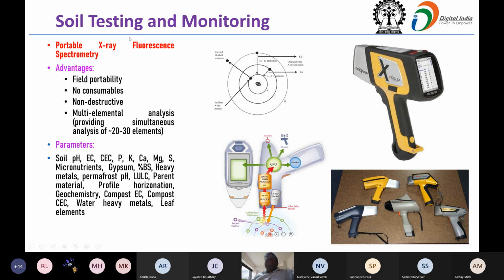Now let us start with the first one, that is called portable X-ray fluorescence spectrometry. It is a very small, handgun type of instrument, and you can see the size. You can carry this instrument in the field, touch its nose to the surface of the soil and press the trigger. It will give you the reading of total elemental content of the soil within only 60 to 90 seconds.